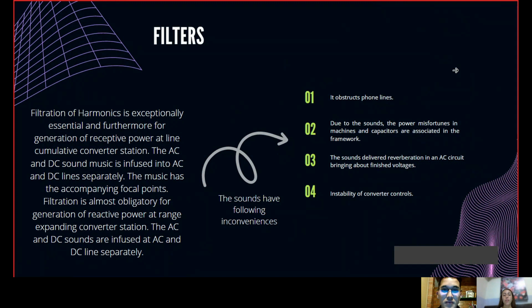Filters. Filtration of harmonics is extremely essential, and also for generation of reactive power at the line-commutated converter station. The AC and DC filters are injected into the AC and DC lines respectively. The filters have the following advantages. Filtration is almost obligatory for generation of reactive power at the converter station.